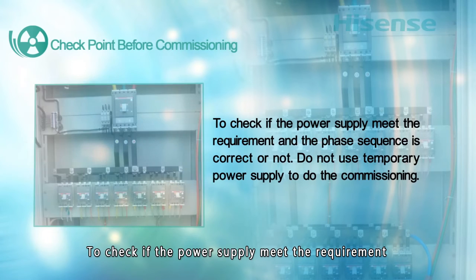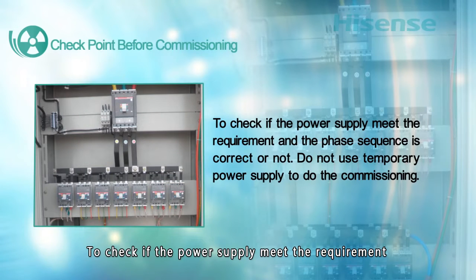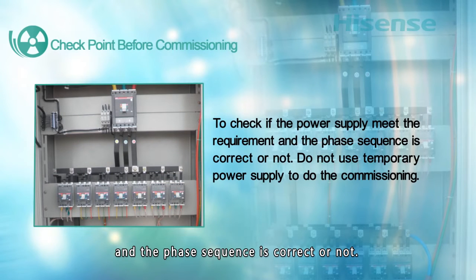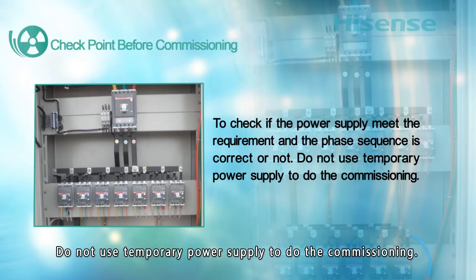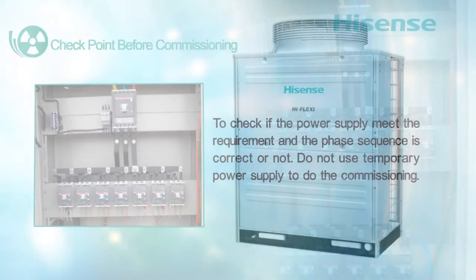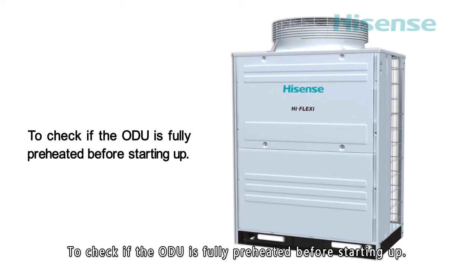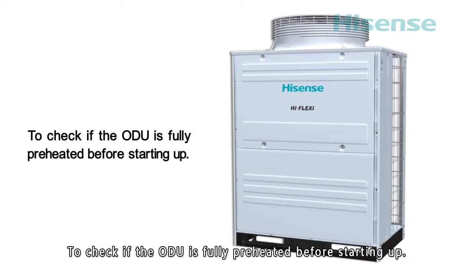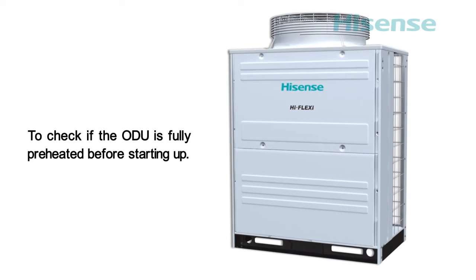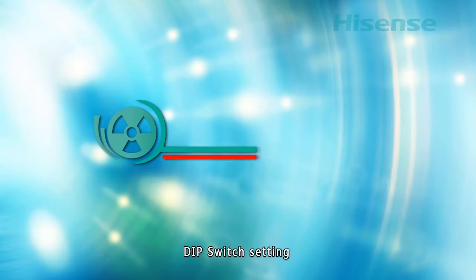12. To check if the power supply meets the requirement and the phase sequence is correct or not. Do not use temporary power supply to do the commissioning. 13. To check if the outdoor unit is fully preheated before starting up. Dip switch setting.